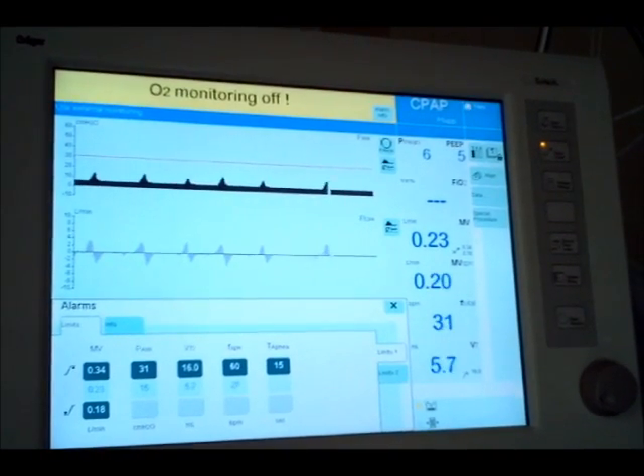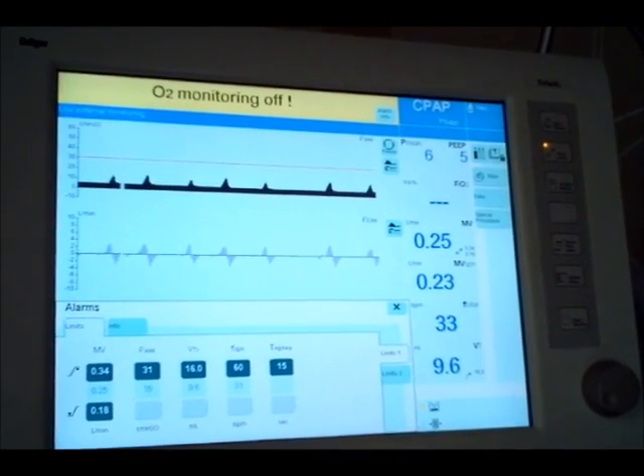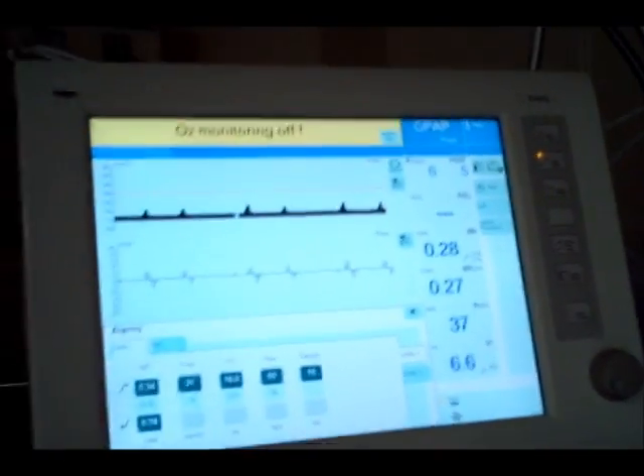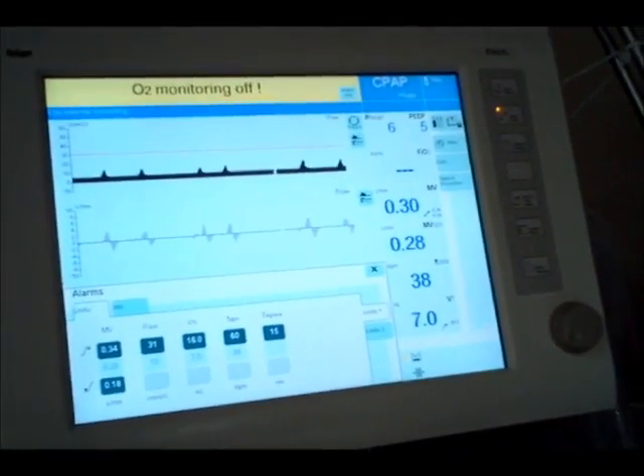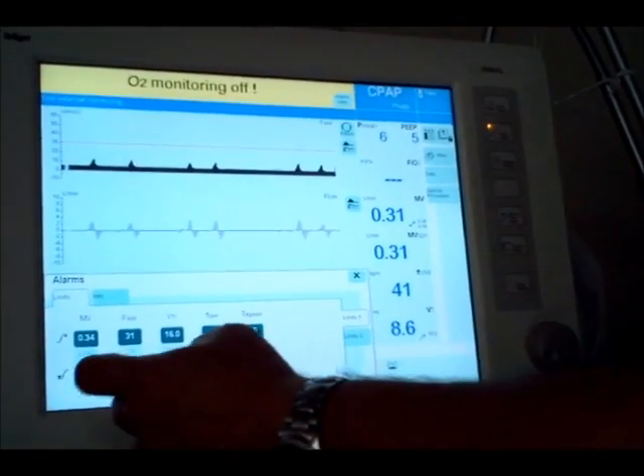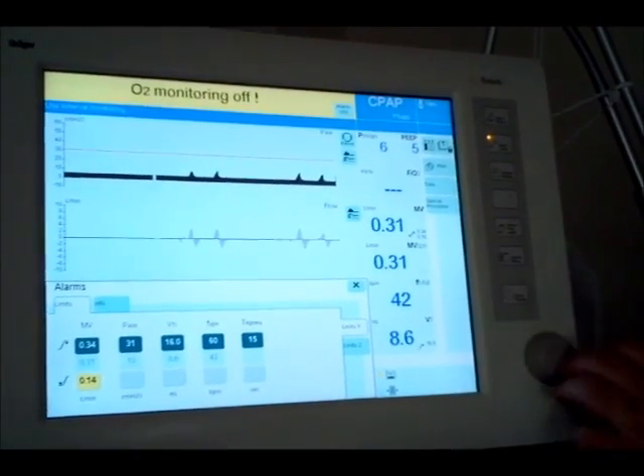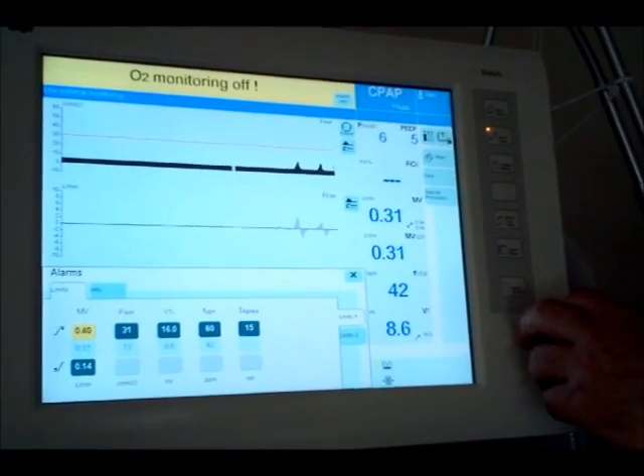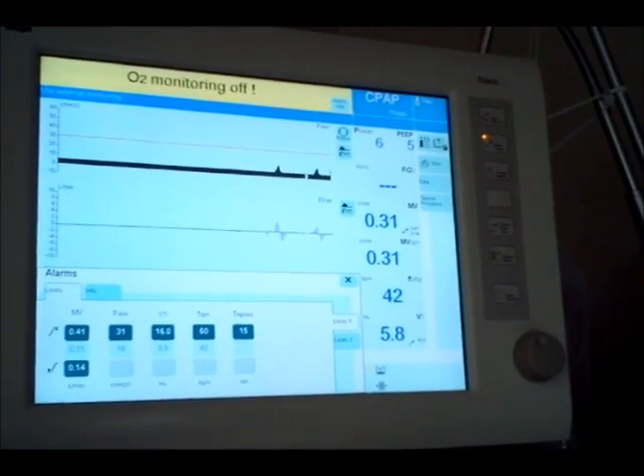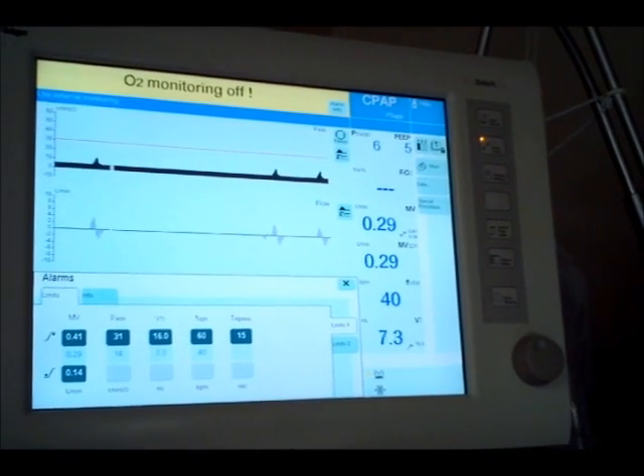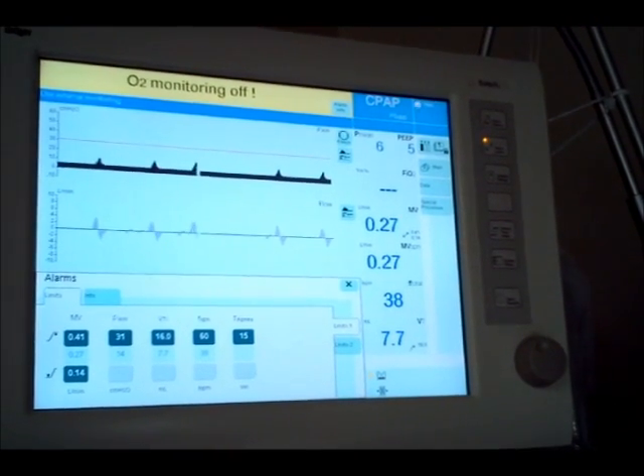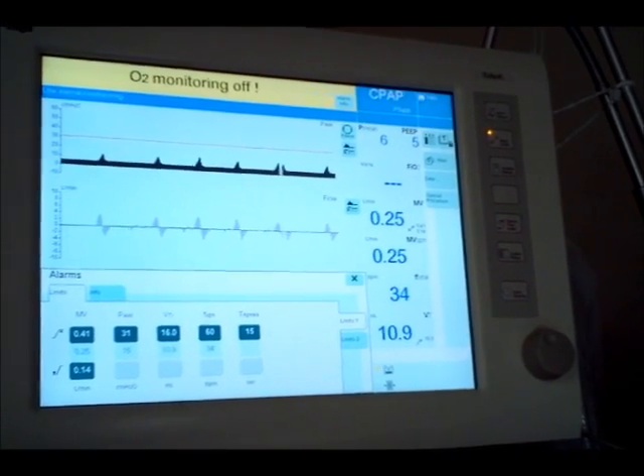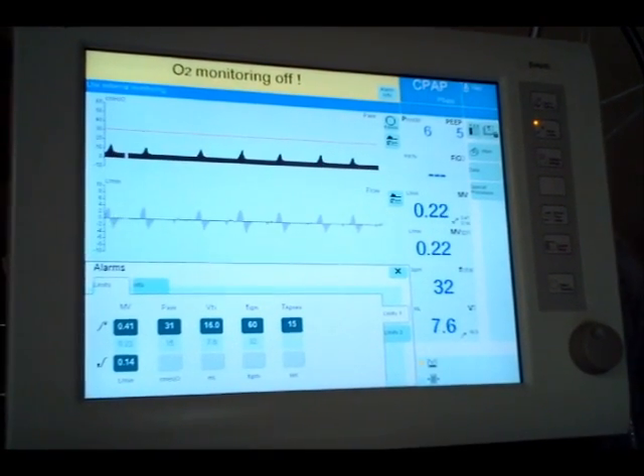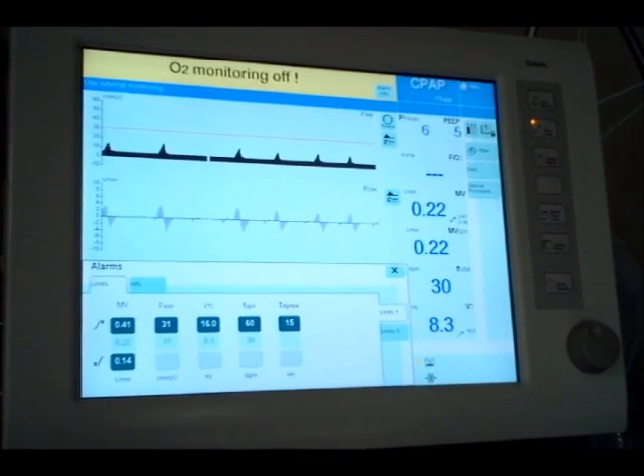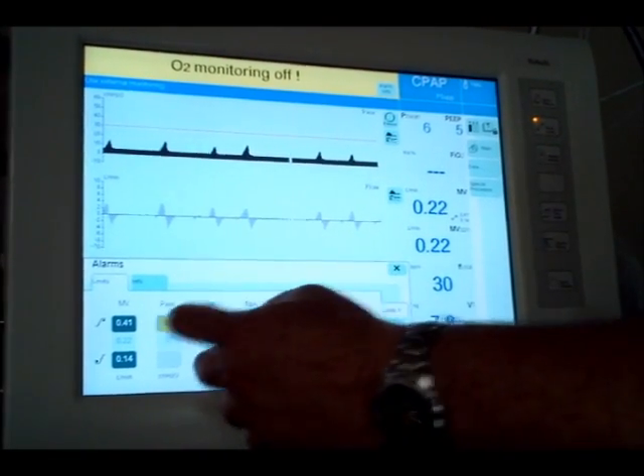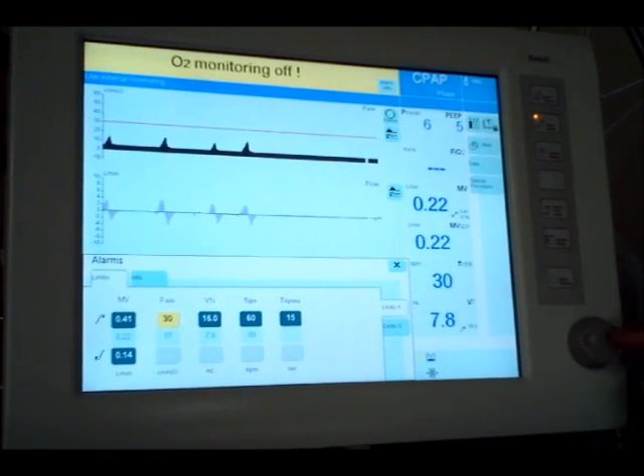We'll go to our alarms. Like I said, in CPAP or pressure support, those totally spontaneous modes, your minute volume is going to vary quite a bit more than in the others. So I'm going to maybe set this a little bit lower and this a little bit higher, especially now that I've stopped breathing, it's going to vary a lot. My peak airway pressure shouldn't really be much higher than 20. So I'm going to leave this at maybe 30, just a nice even number.